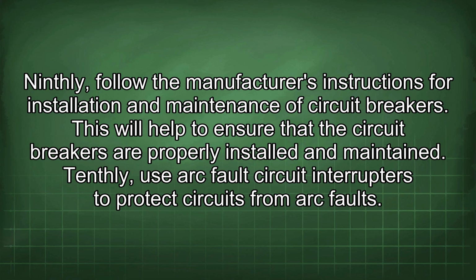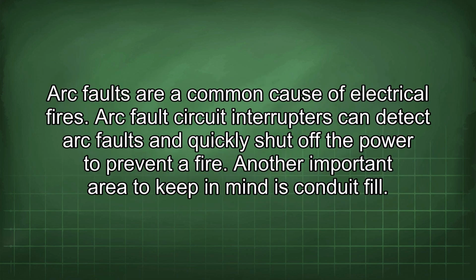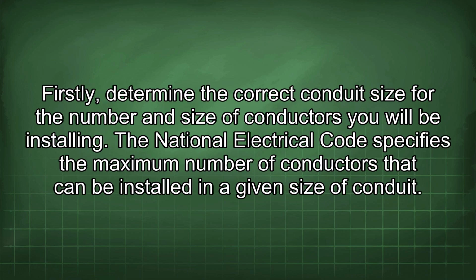Tenthly, use arc fault circuit interrupters to protect circuits from arc faults. Arc faults are a common cause of electrical fires. Arc fault circuit interrupters can detect arc faults and quickly shut off the power to prevent a fire. Another important area to keep in mind is conduit fill. Firstly, determine the correct conduit size for the number and size of conductors you will be installing. The National Electrical Code specifies the maximum number of conductors that can be installed in a given size of conduit.